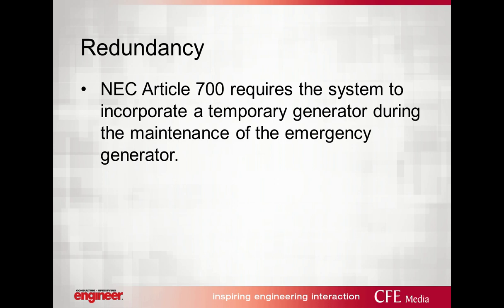Redundancy. So Article 700 now requires the system to incorporate a temporary generator or temporary connection for maintenance of your emergency generator. What that means is if you have a simple system, and we'll just say that you have a generator that's connected to a single transfer switch that's Article 700 required, you need to provide a backup generator for when this thing is being maintained so that the building can still be occupied under normal conditions. So, there's equipment that's made now, transfer switches that have lugs to plug in a separate generator. There's switchboards that are made to have a separate cam-locked connection for a temporary generator to be brought in.